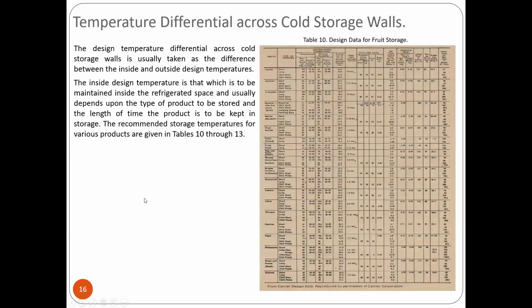Now next, temperature difference across the cold storage wall, similar to the climate. The design temperature difference across a cold storage wall is usually taken as the difference between the inside and outside temperatures. The inside temperature is that which is to be maintained inside the refrigerated space and usually depends upon the type of product to be stored and the length of time the product is to be kept in storage. The recommended storage temperatures for various products are given in tables 10 to 13.